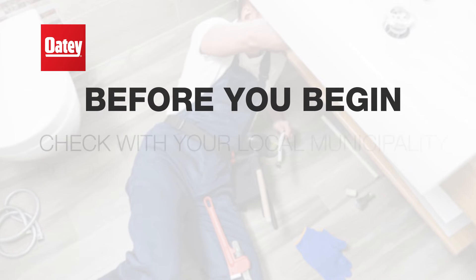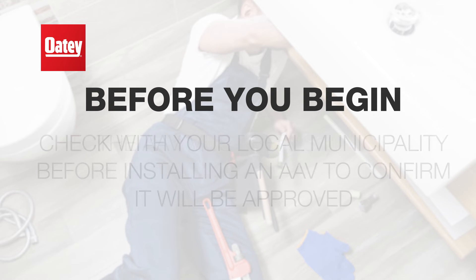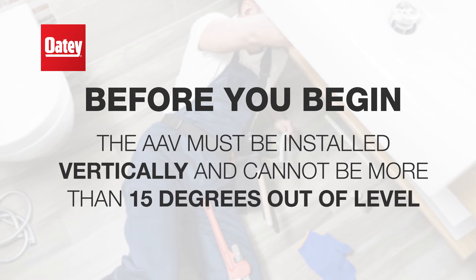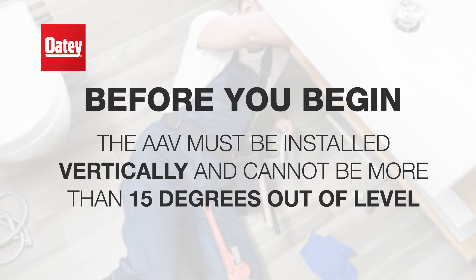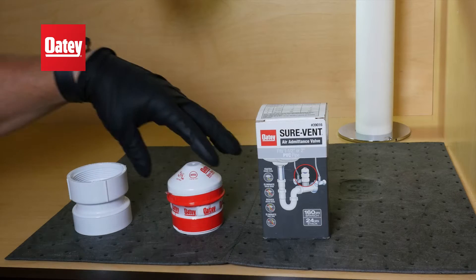Before you begin, be sure to check with your local municipality before installing an AAV to confirm it will be approved. The AAV must be installed vertically and cannot be more than 15 degrees out of level. Also, determine the DFU load of the fixture or fixtures in order to choose the correct Oatey Sure-Vent AAV.